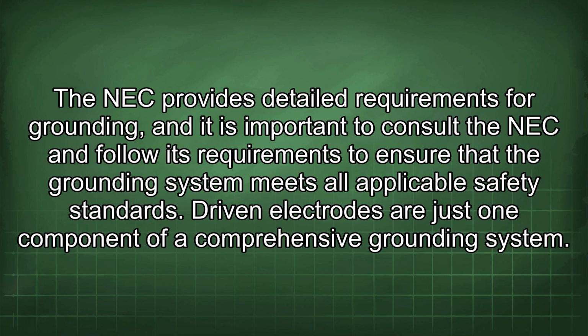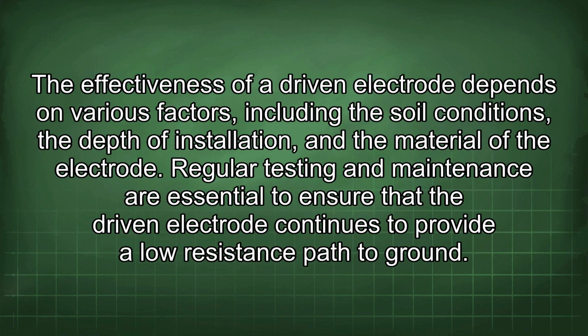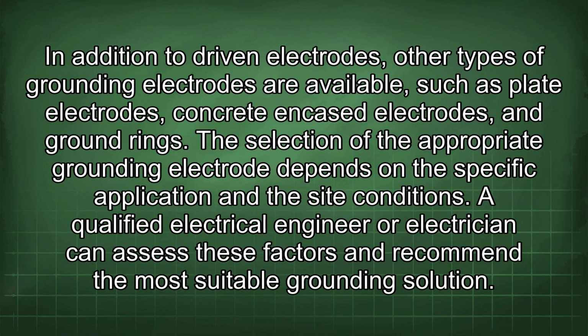Driven electrodes are just one component of a comprehensive grounding system. The effectiveness of a driven electrode depends on various factors, including the soil conditions, the depth of installation, and the material of the electrode. Regular testing and maintenance are essential to ensure that the driven electrode continues to provide a low-resistance path to ground. In addition to driven electrodes, other types of grounding electrodes are available, such as plate electrodes, concrete encased electrodes, and ground rings. The selection of the appropriate grounding electrode depends on the specific application and the site conditions. A qualified electrical engineer or electrician can assess these factors and recommend the most suitable grounding solution.